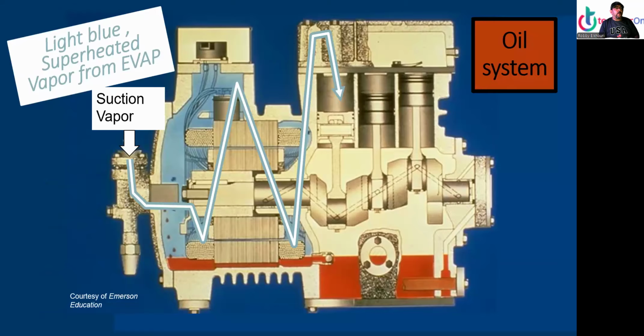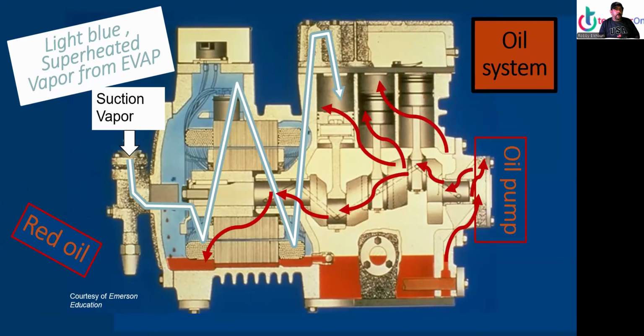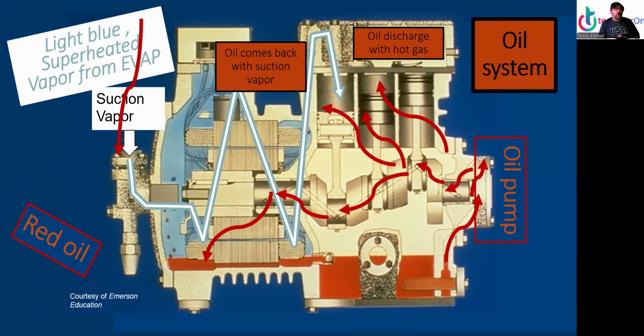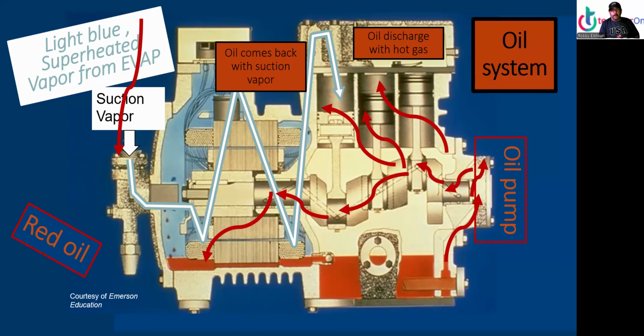Alrighty, so light blue is superheated vapor from the evaporator. In this case, light blue is vapor refrigerant, and the red is oil. And there's the oil pump. The oil pump moves the oil everywhere. Some of the oil also goes out with the hot gas, oil discharge. Oil comes back with the suction vapor also. Oil is in the system everywhere.